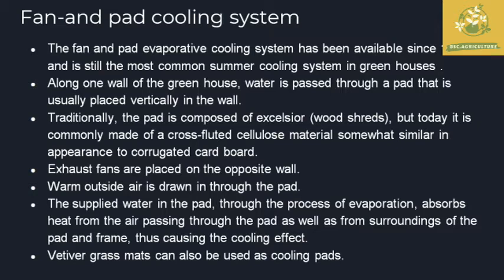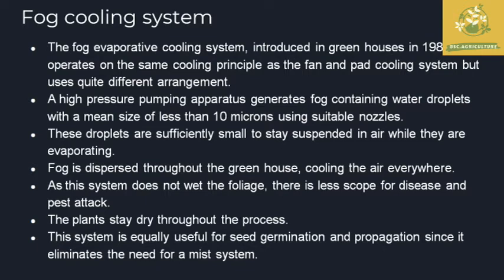Now there is a cross-fluted cellulose material similar to corrugated cardboard material that you can use to maintain the pad system. The exhaust fans are on the opposite wall from the pads. The cooling system works inside the greenhouse: water passes through the pads, and through the evaporation process the water vapor moves into the environment, cooling the air. The wet bulb temperature drives this temperature change. Alternatives include vetiver grass mats, and these are alternative cooling pads compared to the fan-and-pad system, though there are quite different arrangements.